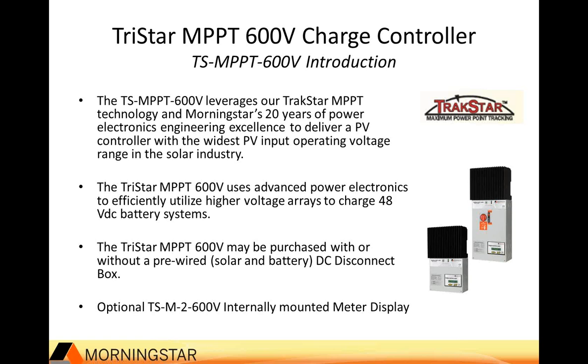It uses our TrakStar MPPT tracking technology, and that's something that's been used on our SunSaver MPPT, TriStar MPPT 150, and now this product. It is basically a very high-speed sweeping algorithm that will find the maximum power point extremely quickly on anything up to a 600 volt array. So ideally, it does not require any type of dynamic tracking or any of the slower technologies that are out there. It finds the maximum power point extremely quickly and stays on it through any kind of shading or other changes in irradiance.